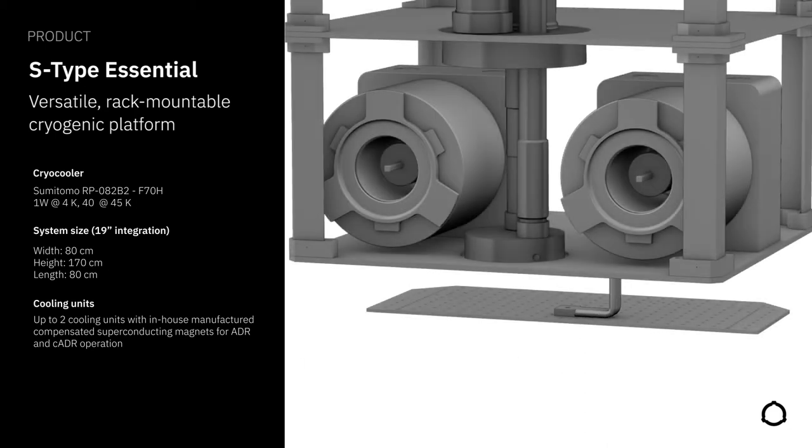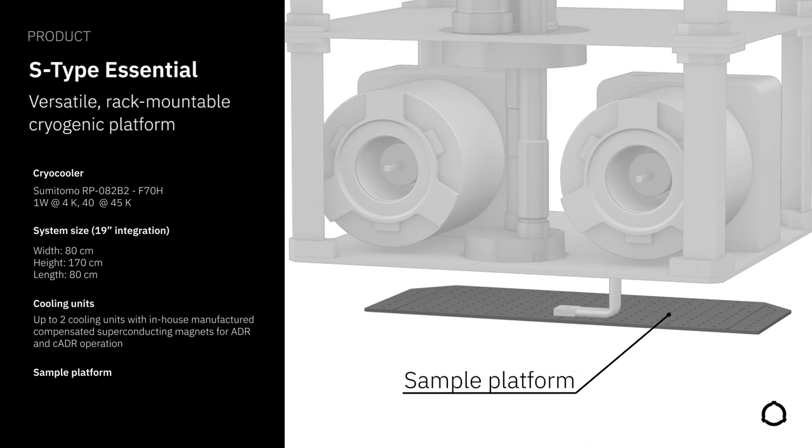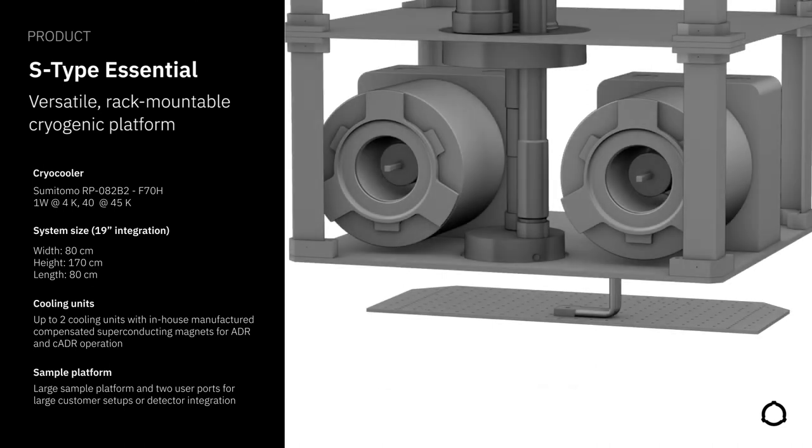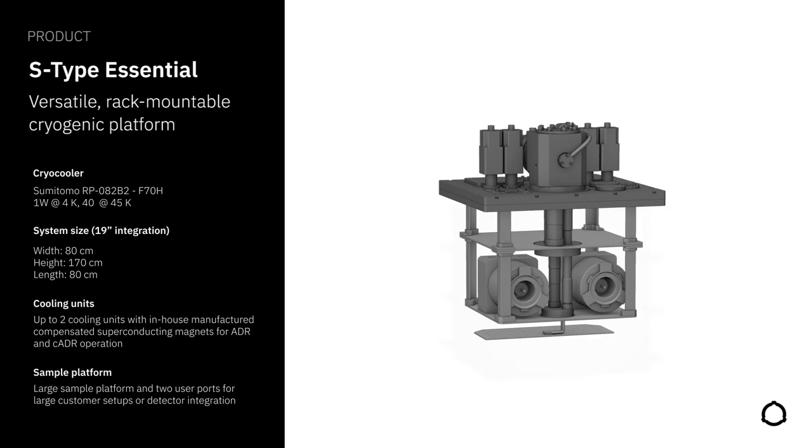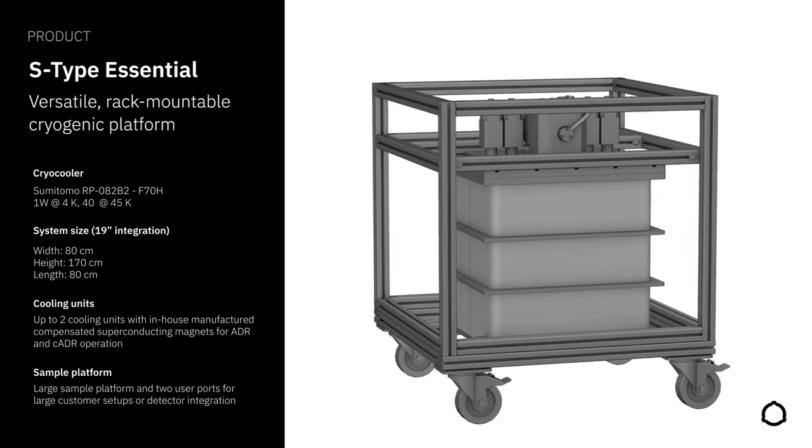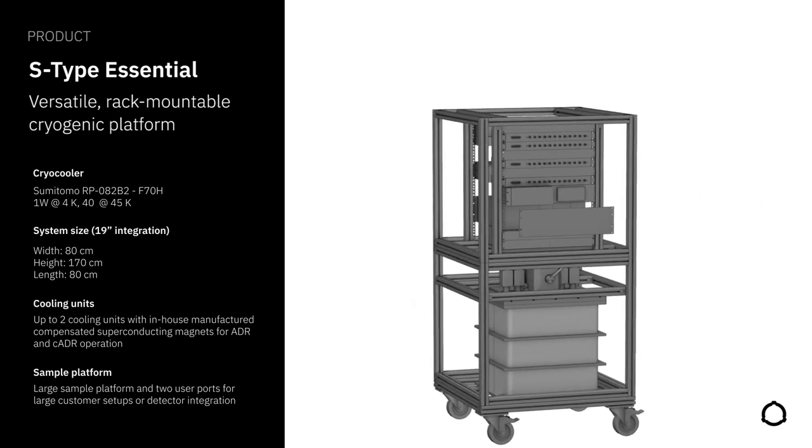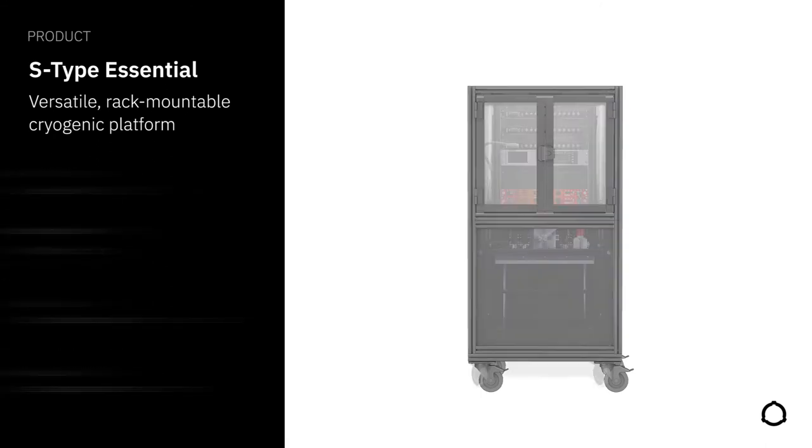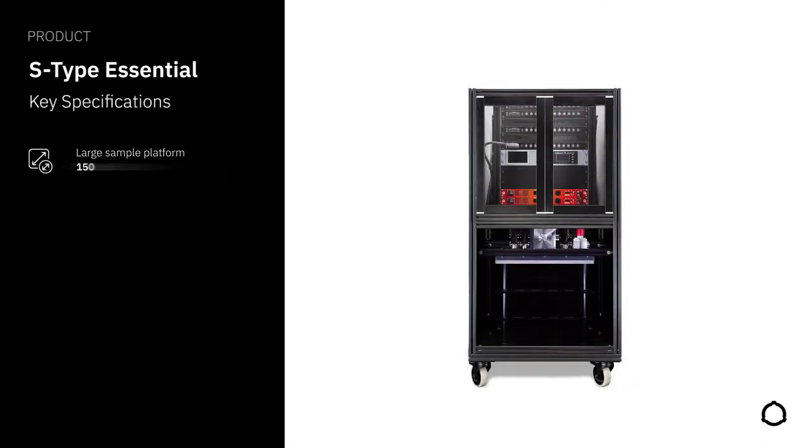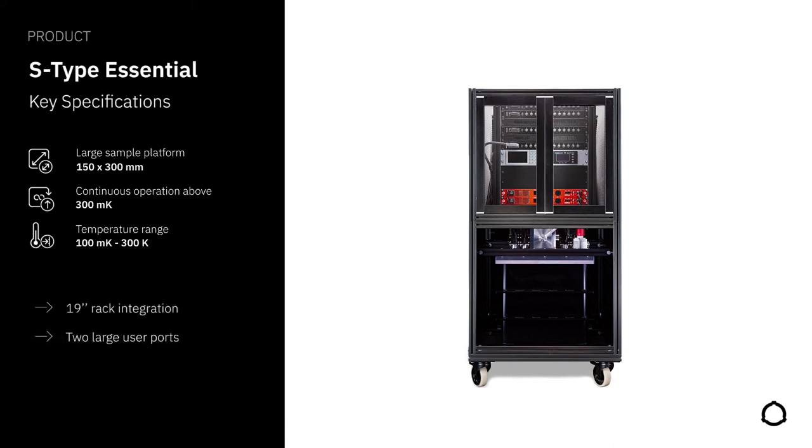While the magnet and the heat switch are mounted onto the 4K plate, the cooling medium is thermally connected to the sample stage to cool the experimental setup. The S-Type Essential offers a large, rectangular sample platform which can accommodate a complex customer setup, detector arrays or other low temperature electronics. Finally, the system is mounted in a modular 19-inch rack with one module holding the cryostat and another module including all system electronics as well as space for customer electronics. In this configuration, the S-Type Essential offers continuous cooling at 300 mK and one-shot operation down to 100 mK with a hold time exceeding 3 hours. Additionally, the system features one large sample platform and two large user ports for custom wiring such as RF lines or optical fibers.